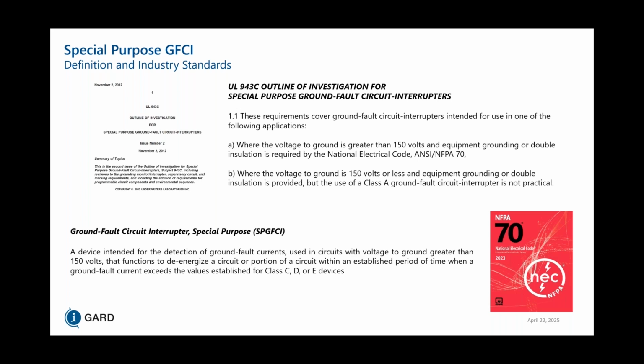The first one is where the voltage to ground is greater than 150 volts and equipment grounding or double insulation is required by the National Electrical Code, as well as ANSI/NFPA 70E. And the other one is where the voltage to ground is 150 volts or less and equipment grounding or double insulation is provided, but the use of a Class A ground fault circuit interrupter is not practical, which is like your standard Class A GFCI that trips at 6 milliamp.